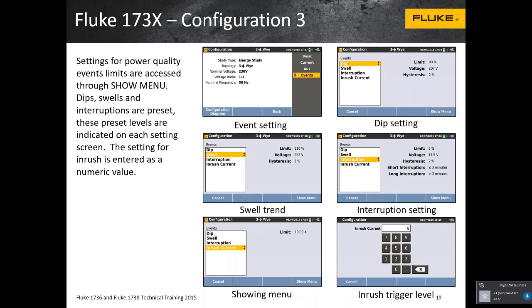The difference is that when you set up a recording session in the 32 or the 34, you tell it how often you want to store the min, max, and average measurements you're taking. Depending on that period, you'll know the maximum measurement that took place within a certain time period, but you won't know how long it was or exactly when it started or ended, and you won't have the ability to capture multiple events in a time period. With the 1736 and 1738, they capture dips, swells, and interruptions.